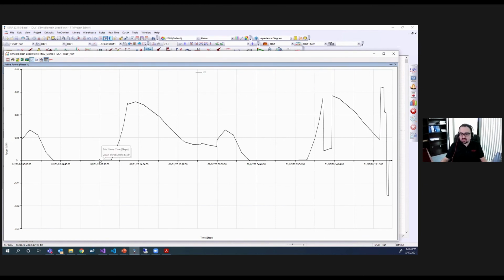The same scenario for the second day. As you can see, we are charging the batteries and we are discharging the batteries. But on the second day, because we have a planned islanding request from the ADMS, before the system goes to islanded mode, during the time that it is not peak time, based on an optimization logic, the Microgrid controller is charging the batteries to increase their state of charge.